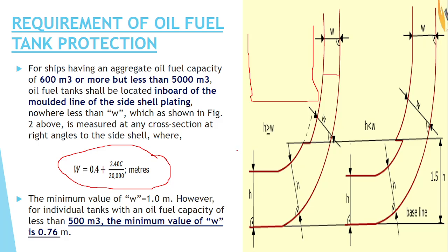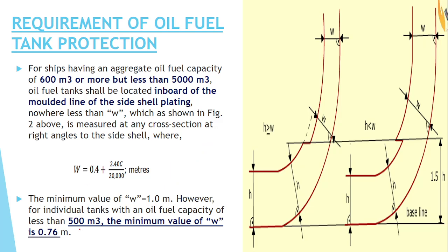So if the formula gives 2 metres, you can take 2 metres. But if it gives 0.9m, you cannot take 0.9m — you have to take 1 metre. The second case says: if your fuel oil capacity is less than 500m³, in that case you can take 0.76m.